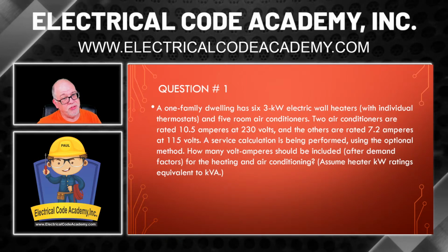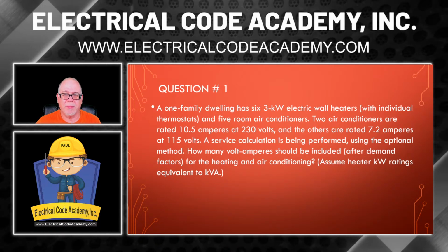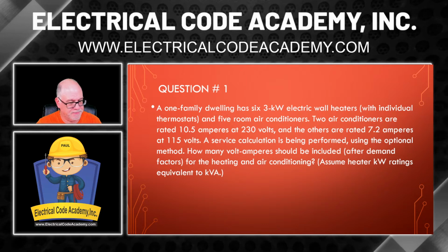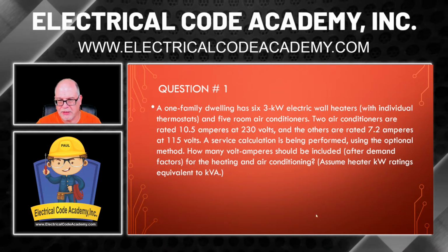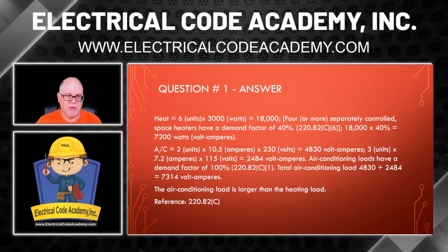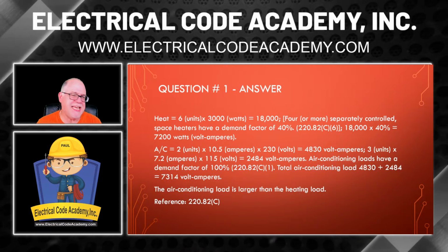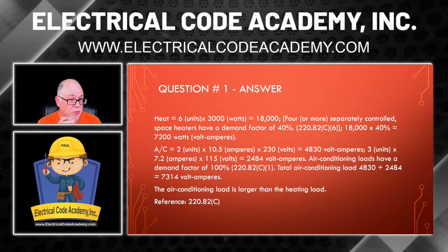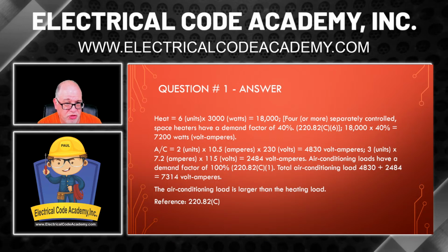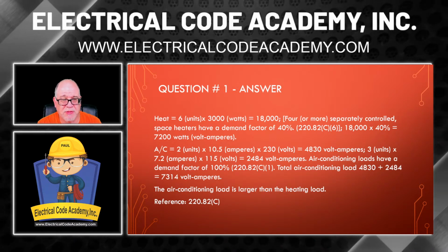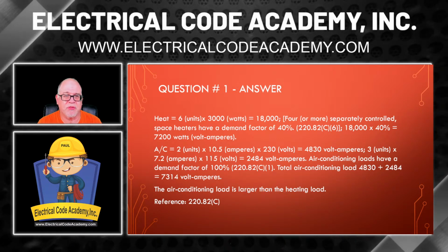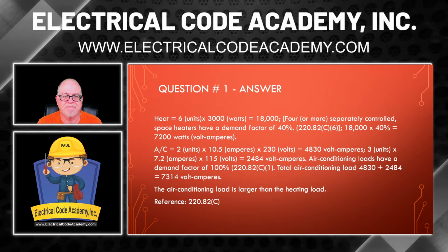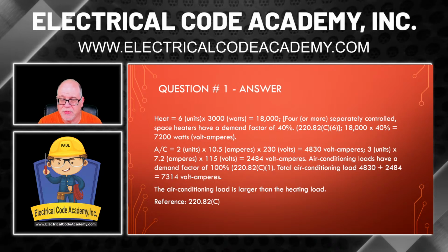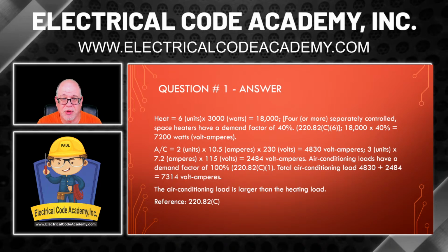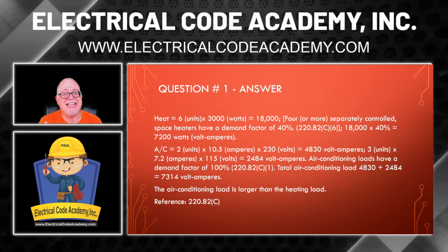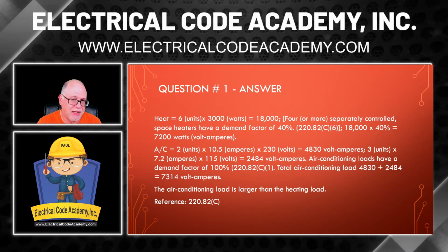So here was our question, and we got to do a couple things in order to get there. All right, so let's go on and start working the math. First thing, let's knock that heat out. There were 6 of them, 3,000 watts each, or 3 kW each. So we're going to work this out. 6 times 3,000, or 6 times 3 kW, would equal 18 kW. But in this case, it's 18,000, the way we're working it out here.